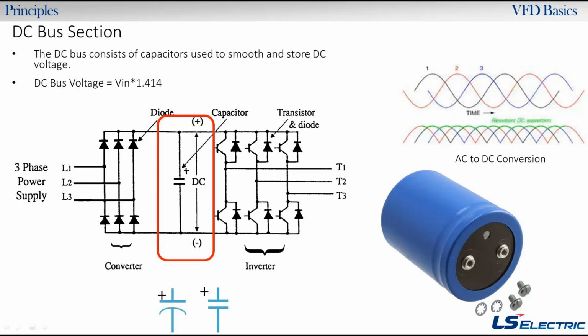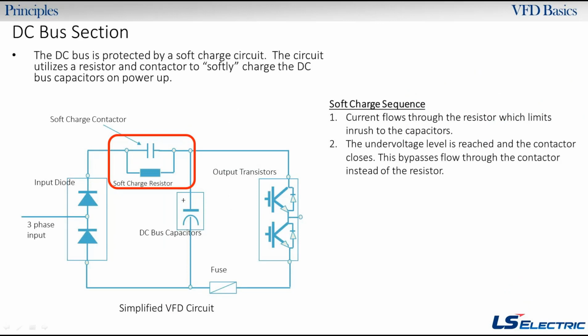All right. So here's a little bit more about the DC bus section. We also have something called a soft charge resistor or a soft charge circuit. People also call it a pre-charge circuit, and I'm sure there are other names for it, but those are the common ones. What this does is it protects your DC bus. Capacitors are electrically seen as a short. So what happens if you apply the full 680 volts, which is that rectified voltage, to a capacitor that's electrically shorted? It's not going to be a good thing. It could blow out the capacitors.